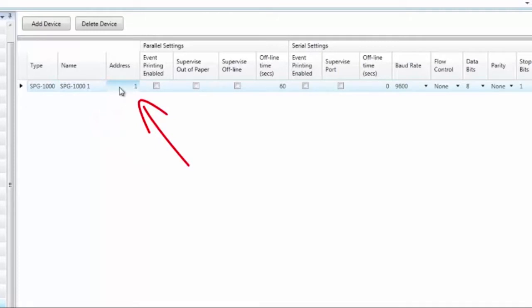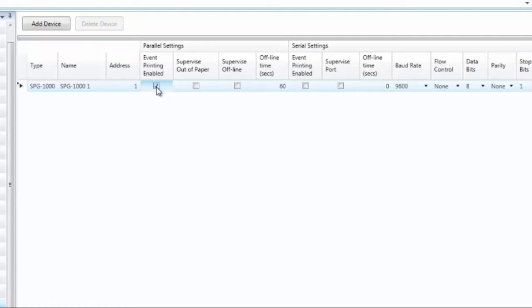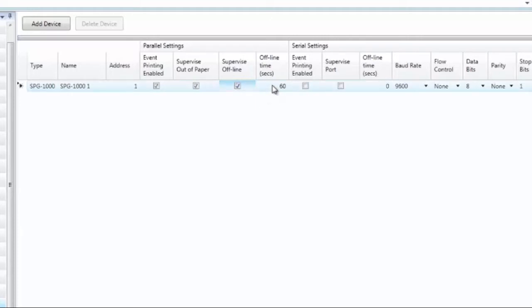You can also change the address — these devices accept any address between 1 and 31. Make sure the DIP switch on the SPG1000 in the field matches the programmed address. If connecting to a parallel printer via DB25, check the box to log events to that printer. Checking the supervised out-of-paper box causes the SPG1000 to continuously monitor the connected printer for an out-of-paper condition, generating a trouble event at the panel when detected. Selecting Supervised Offline causes it to monitor for an offline condition similarly. If Supervised Offline is selected, the offline time sets how long the condition must be present before the trouble event is generated — the default is 60 seconds.